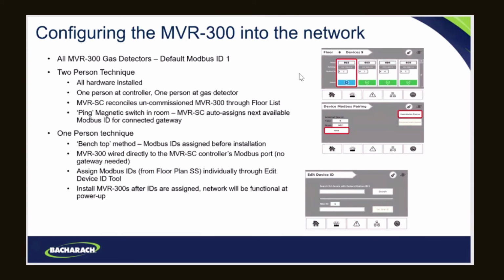Now, once you have that CSV file uploaded to the controller, there are two ways to commission the MVR 300s. There is a two-person technique where all of the hardware is installed. You have a controller on the wall, you have all your network connections made, you have your gateways commissioned, and you have your MVR 300s installed in all of your rooms with the Modbus wiring, the power wiring, and anything wired up to the relays. So everything, all the hardware is deployed.